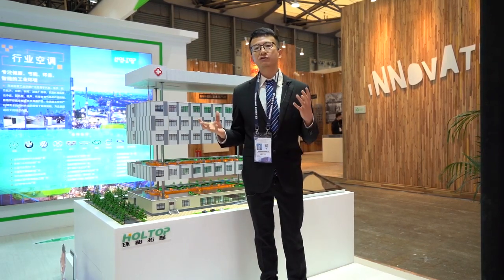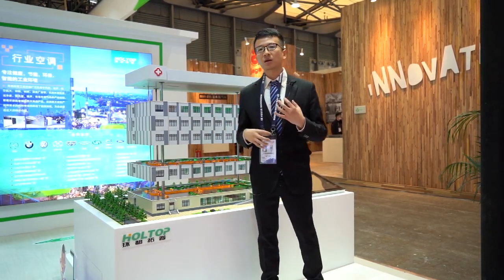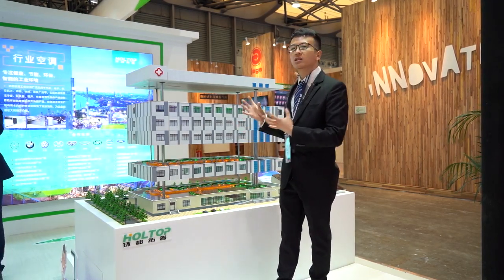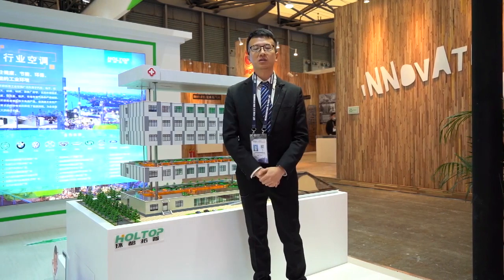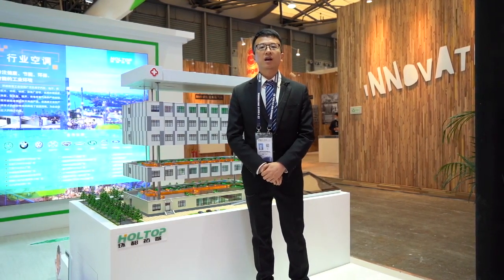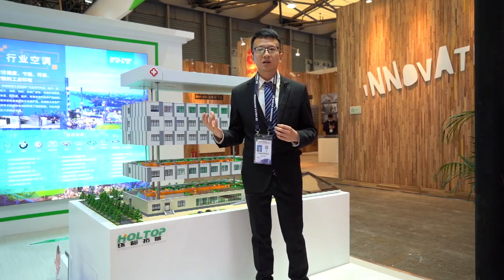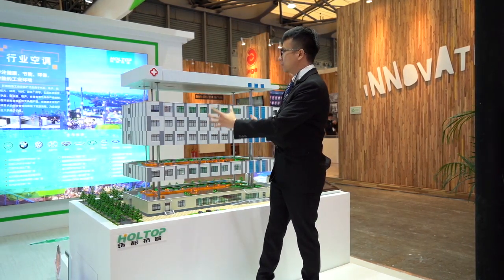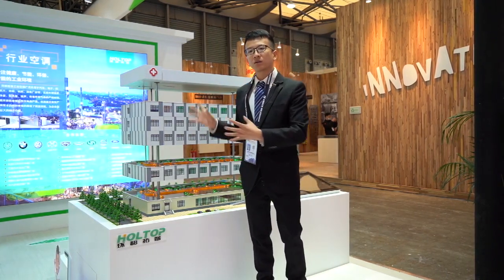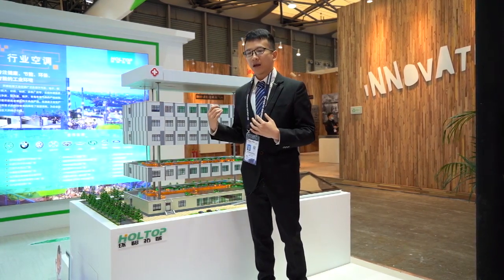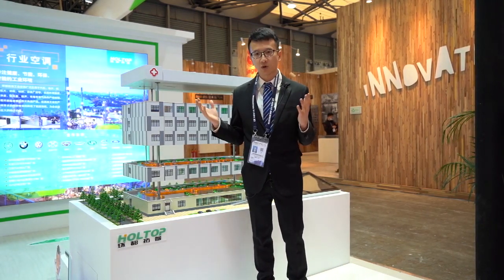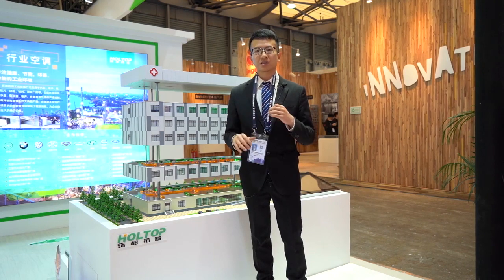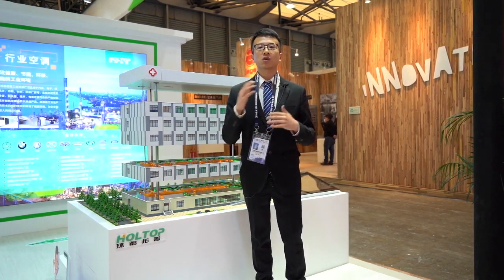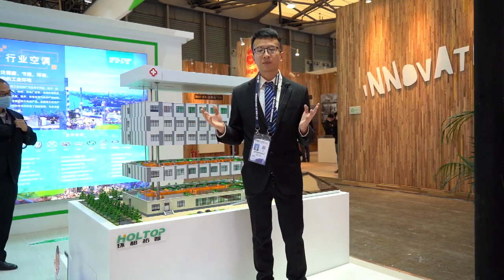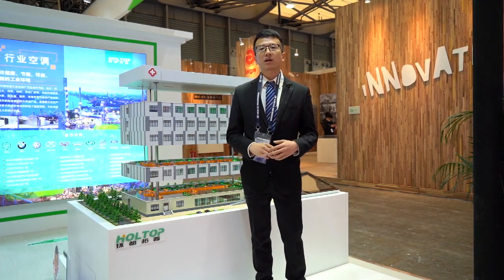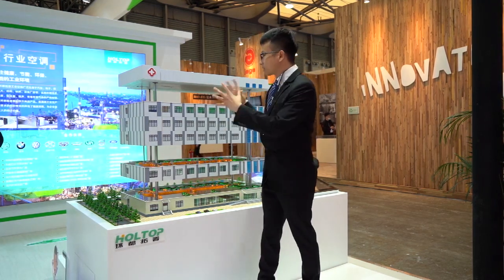Compared to the traditional HVAC design and system in a regular hospital, this new smart fresh air system has 4 advantages. The first one is air quality security, which means the system has a clear design for the fresh air supplying and exhausting air system. These two systems are totally separate, which means the airflow routes are separate to ensure there is no air contamination or air cross flow.